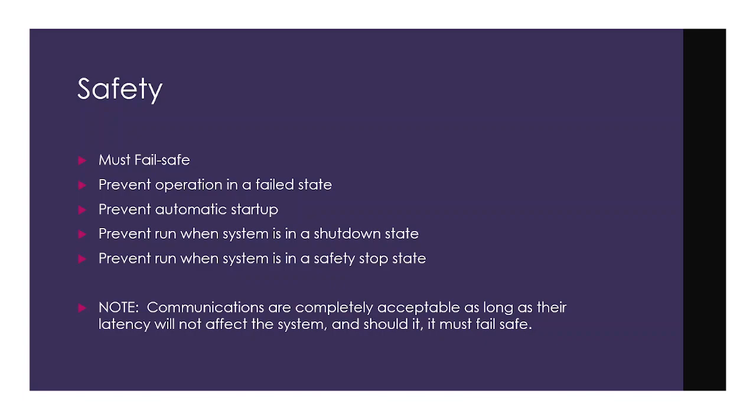So you would create more or less a monitored circuit, and we'll go through some of how that circuitry is designed in some other later videos down the road. But when that circuit is designed, it's designed so that if there's a monitoring circuit that fails somewhere along the way, or it understands that any other pieces failed within the system, that it will keep and prevent the system from re-engaging while it's in that failed state.